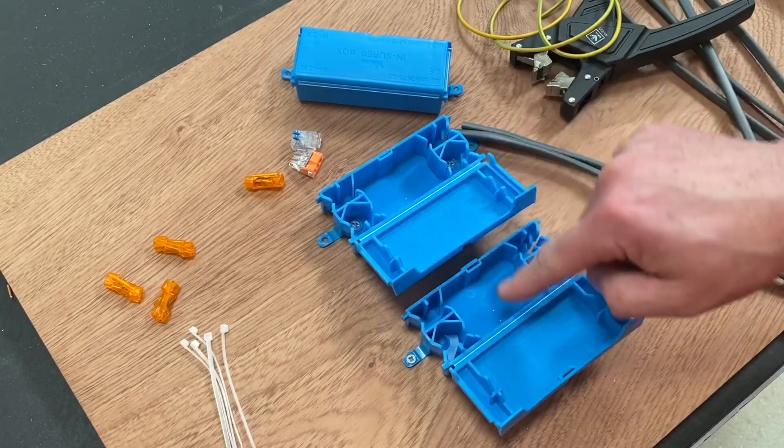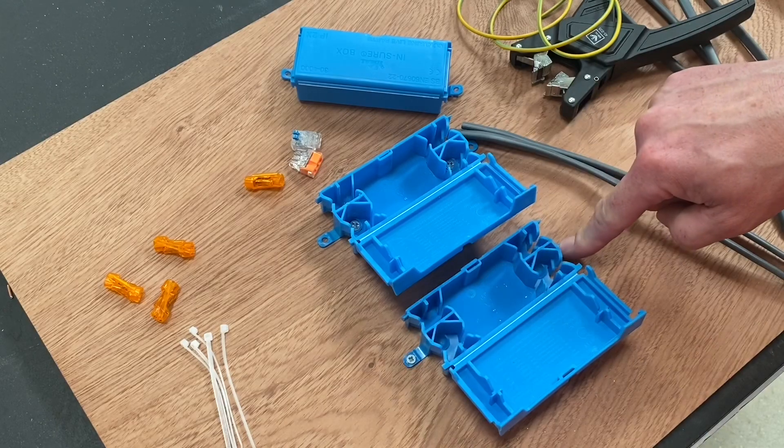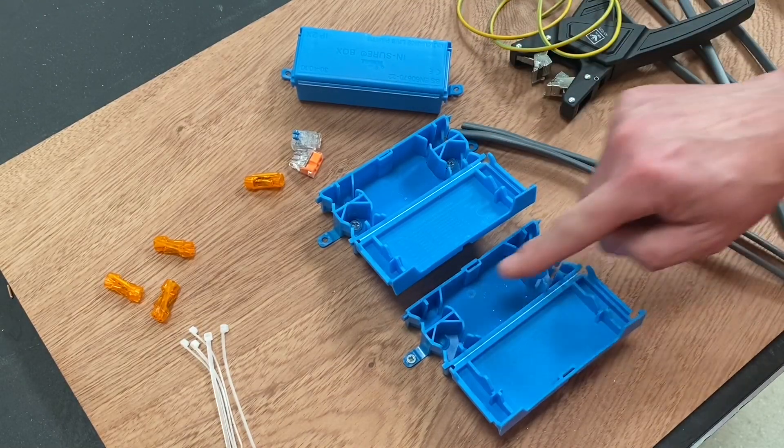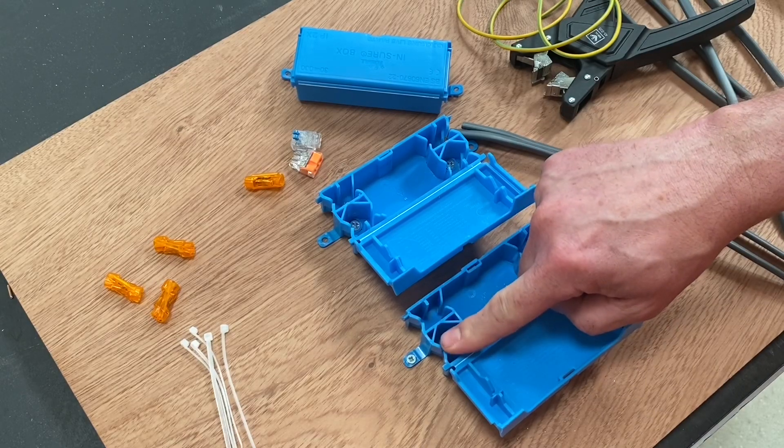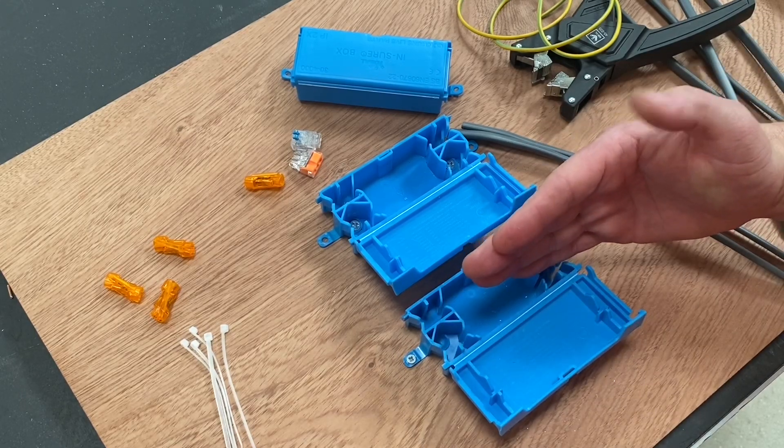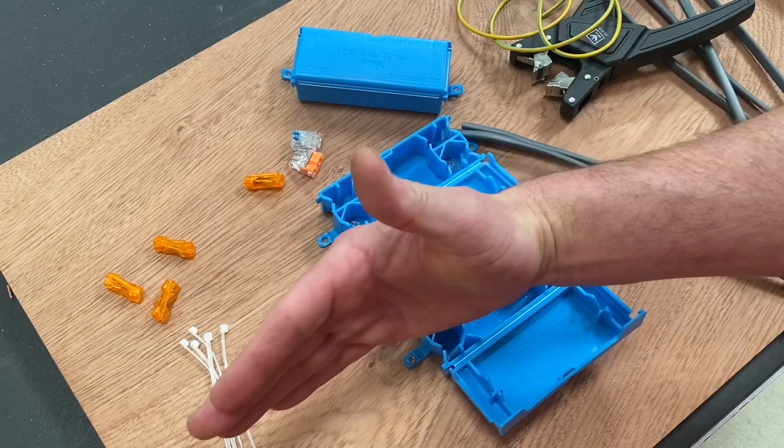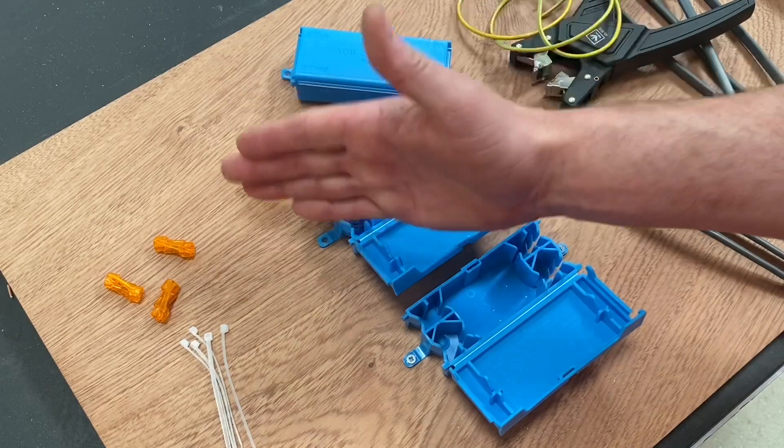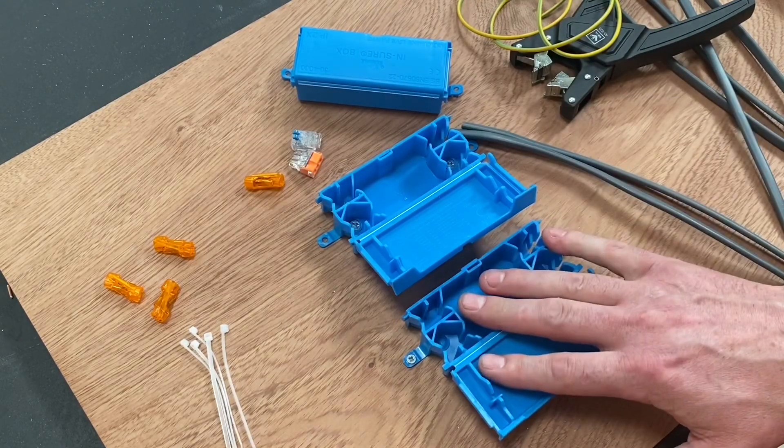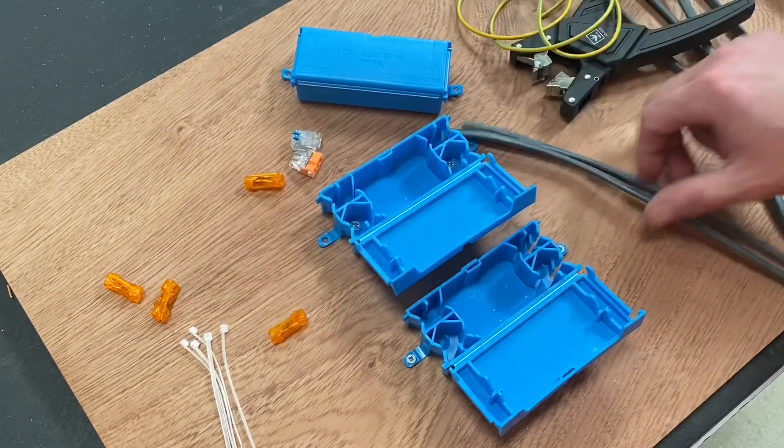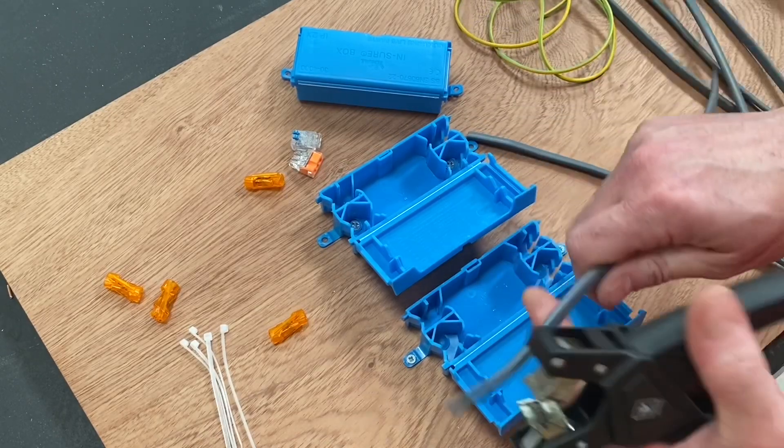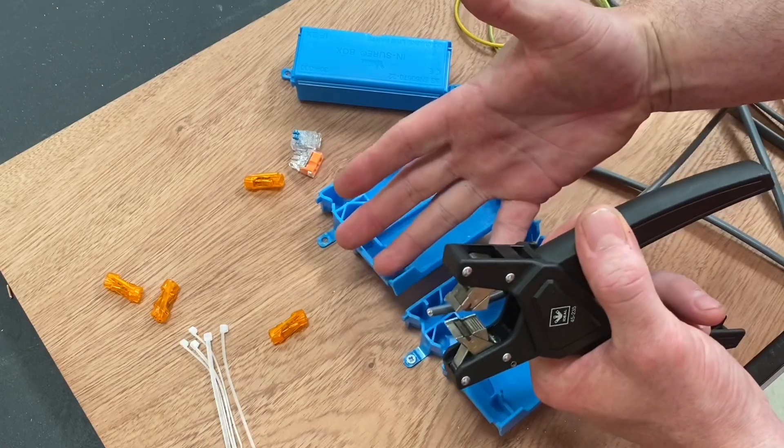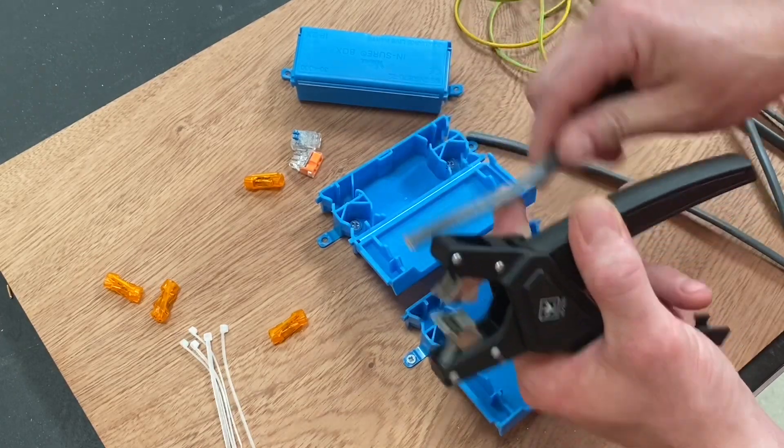So I've screwed down two In-Sure boxes, and I've used the outside fixings on this one and the internal fixings on this one. We've got four positions which we can bring cables in on. What we're going to do in the first instance is join a 1 millimeter squared cable as if you're extending a lighting circuit. So we'll start with this one here. I'm going to use the splices for this connection. As always, you need to make off your cables before putting them into the cord grip. So we're going to make all our connections external to the box and then push them into the box and close it up.